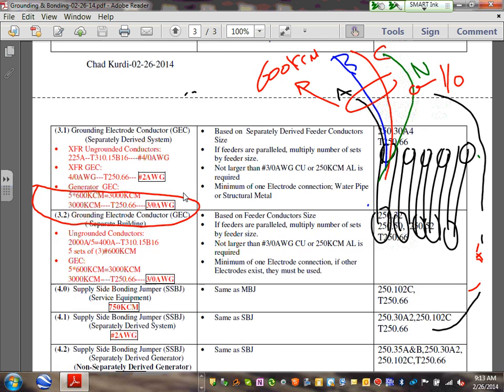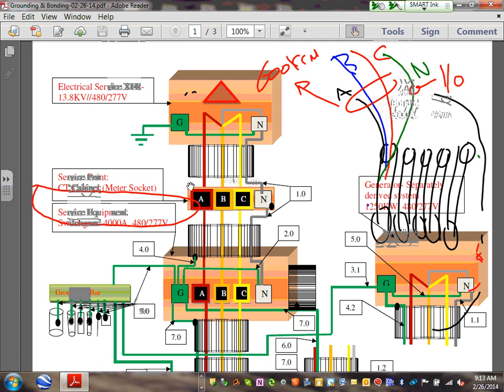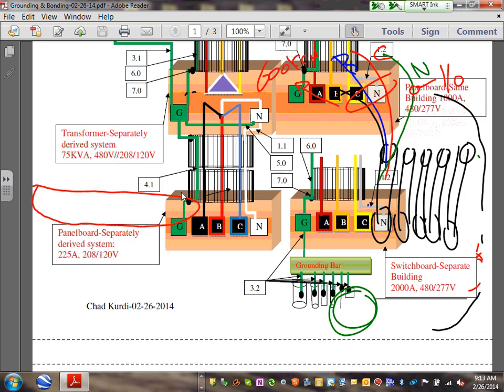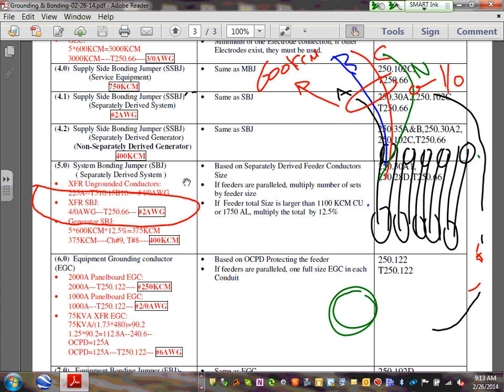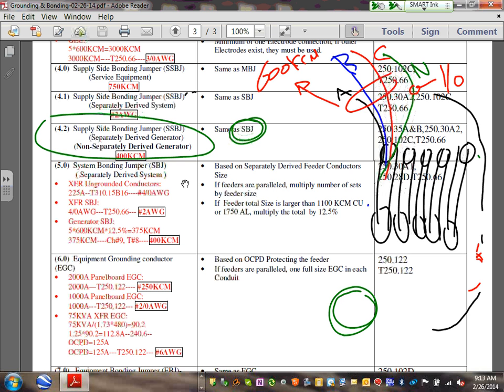Let's go. Okay, so now we're still carrying that. Now I'm going to go to this one here. Can you guys see that? This is called the supply side bonding jumper at the generator, 4.2. Okay, Adam, let's go directly to 4.2. Gentlemen, 4.2 is identical. Can you guys see? Here's 4.2. It's a supply side bonding jumper, separately derived generator, or non-separately derived generator, 400 kcm. It's exactly as the system bonding jumper, and the load channel is identical. So these two are identical. Can you guys see that? So it will be 400 kcm.